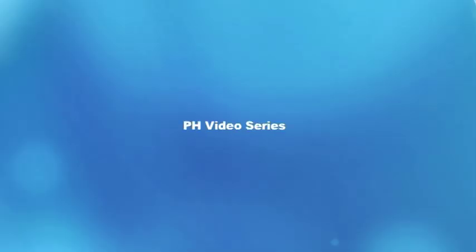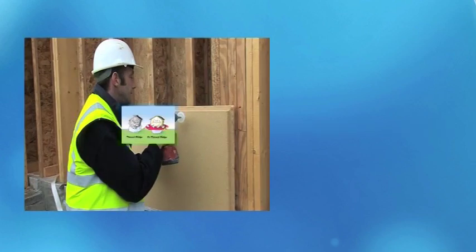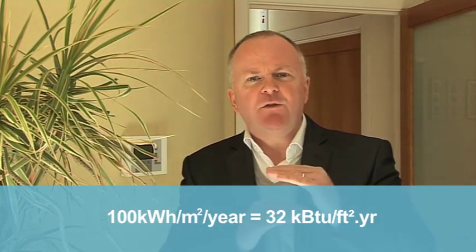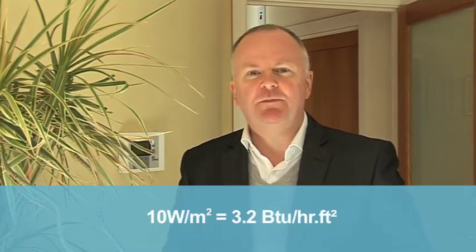Welcome to the last in this series of videos on passive house. Let's reflect on what we've learned so far: the general principles of a good compact building facing the sun, super insulation levels, eliminating thermal bridges, triple-glazed high-performing windows, and heat recovery ventilation. With all these ingredients in our building fabric, we're dramatically reducing our space heat demand from around 100 kWh per square meter per year down to just 15 kWh per square meter per year, and our heating load from 100 watts per square meter down to 10 watts per square meter.